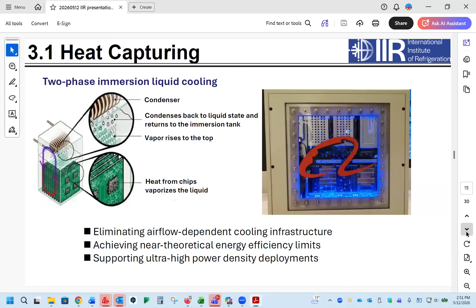But if you want the whole server cooled by liquid, we use immersion cooling. Usually this is single phase immersion cooling, but some companies have developed two-phase immersion cooling, which can divide from single phase to two-phase to increase the heat transfer coefficient and decrease the mass flow rate of the coolant.